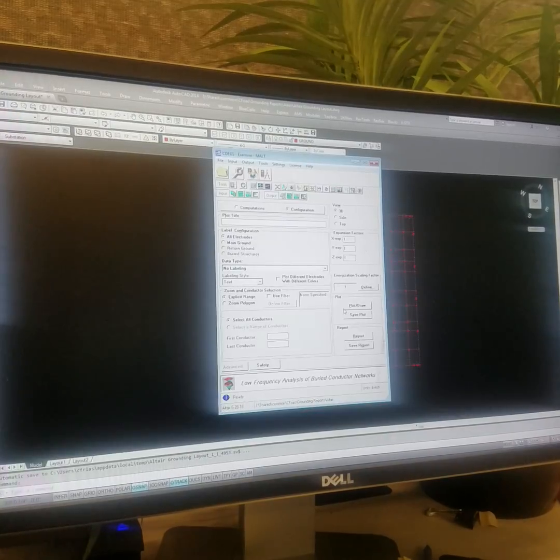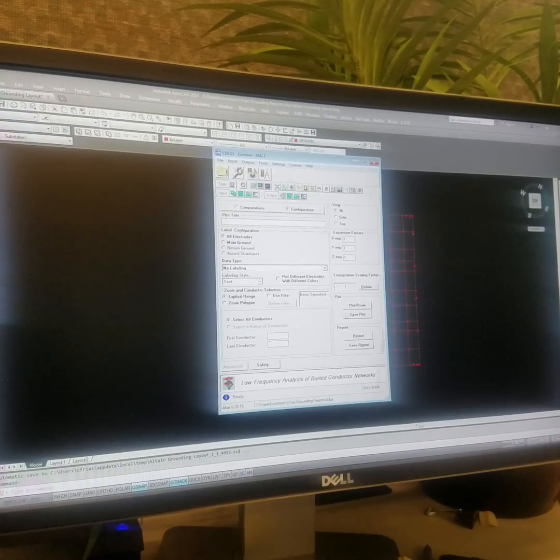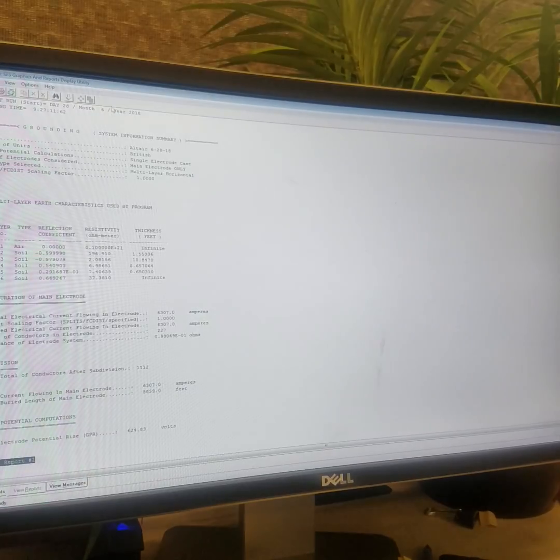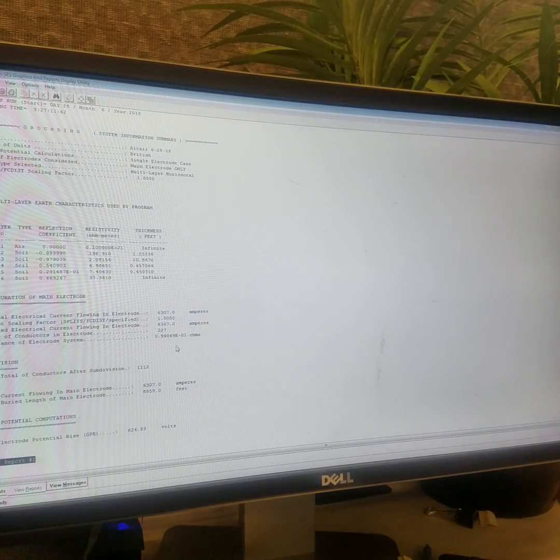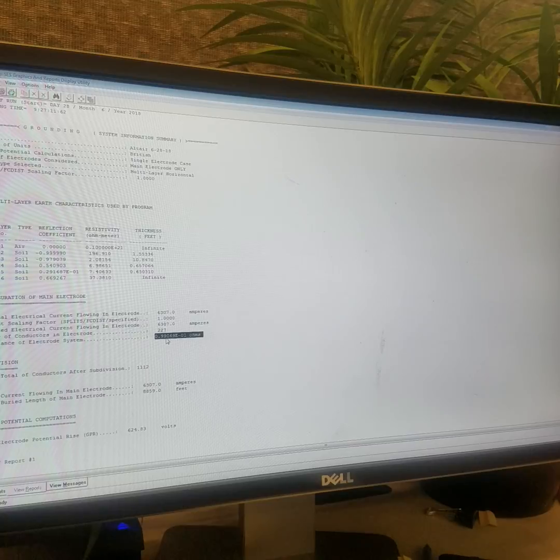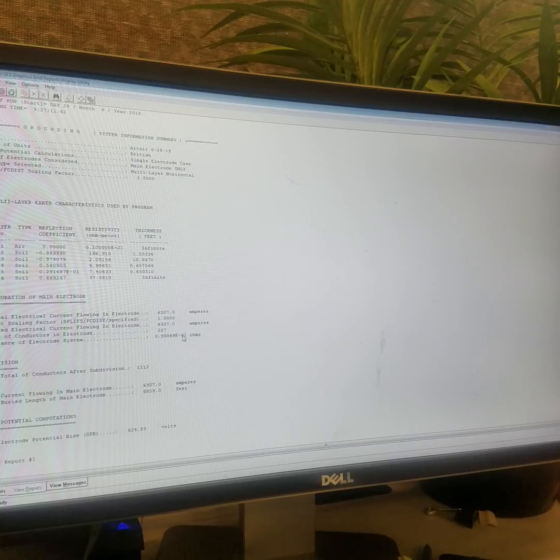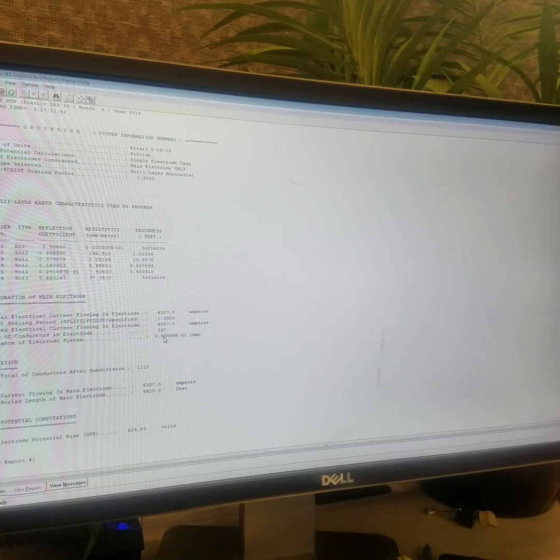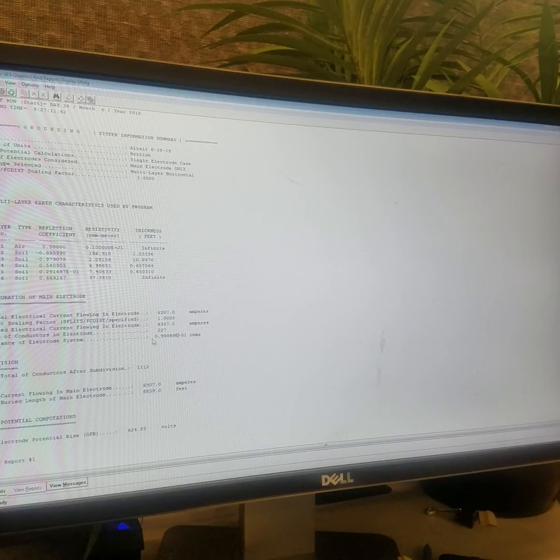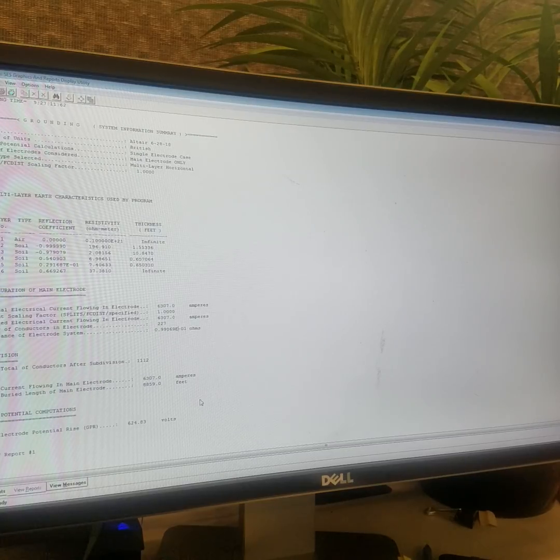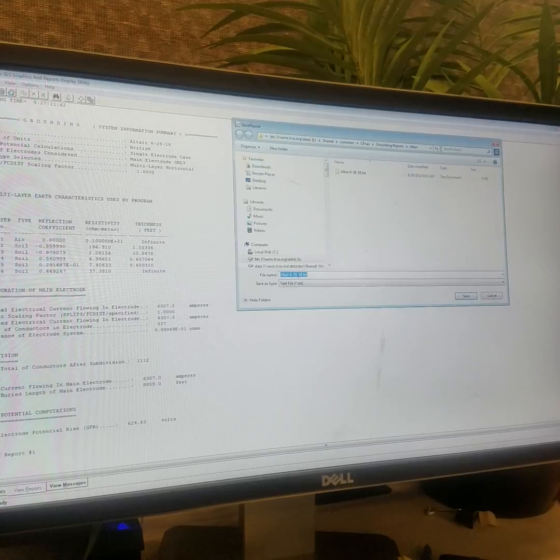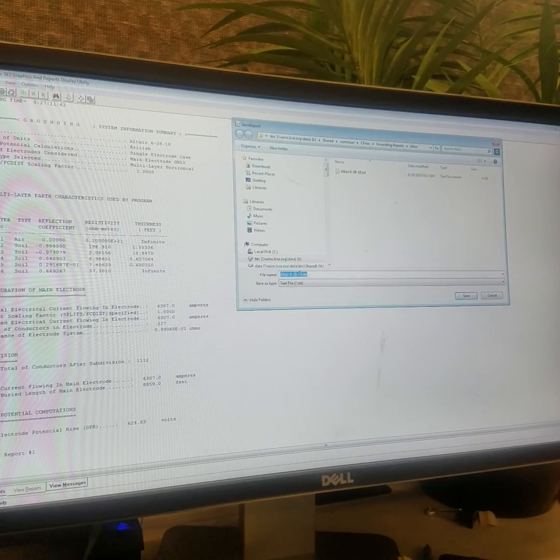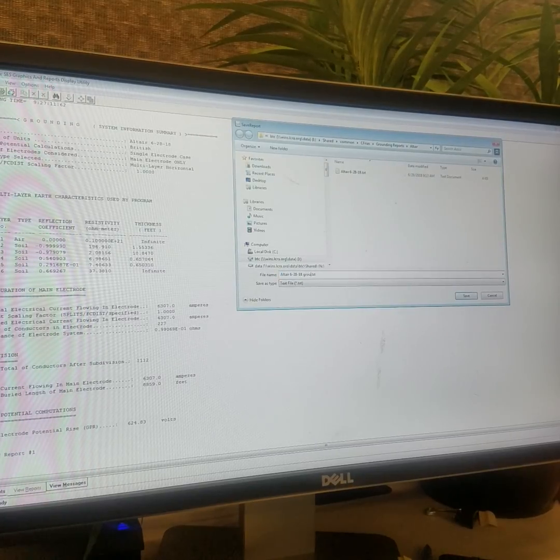All right, so once it looks like it worked great, click your report. That's still pretty good, that's actually really good. I'm sorry, I didn't see this, so it's point zero nine. So point point one almost resistance, which is super good. You go ahead and save this as your grounding report.